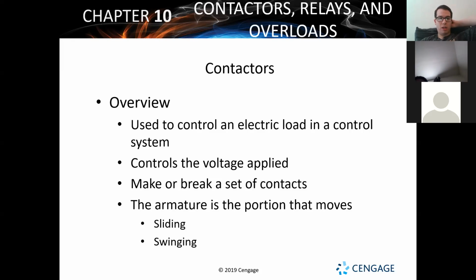All right. So contactors are going to be the main thing that we have controlling our high loads in our system. The compressor is going to be drawing the most electricity in an HVAC system. As far as a residential system or anything that's moving refrigerant around, it's going to be the compressor. To control that, we use a contactor.